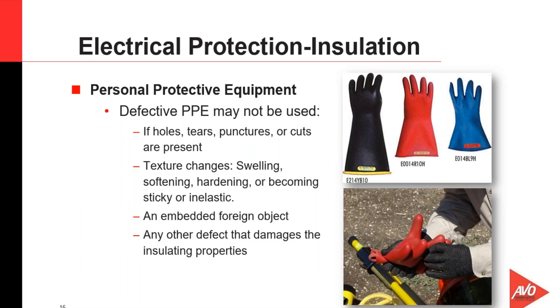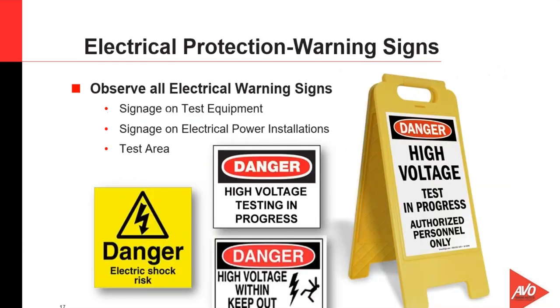Gloves need to be inspected before you use them each day, as demonstrated in the picture of the worker doing a simple air test. It's a simple inspection just to ensure that the gloves don't have a tear or hole or anything like that in them. Gloves are rated from 500 to 35,000 volts and essentially can be used at whatever rating or level that we're actually working on.